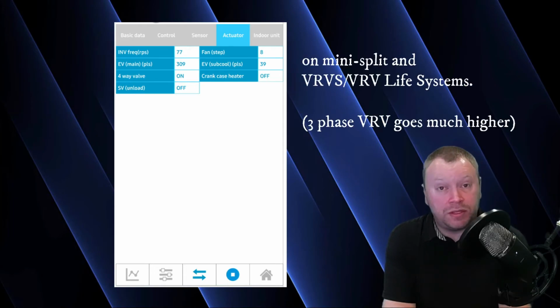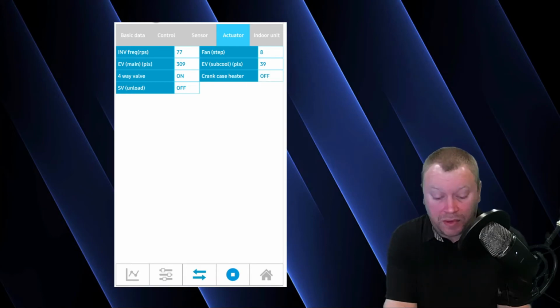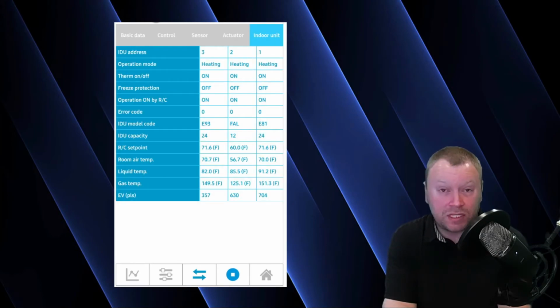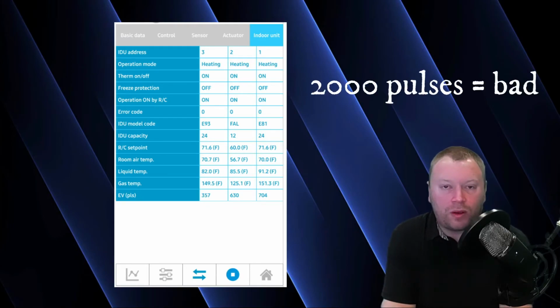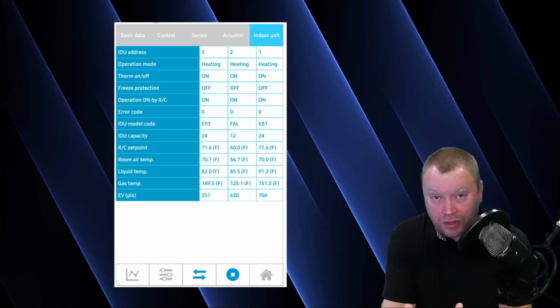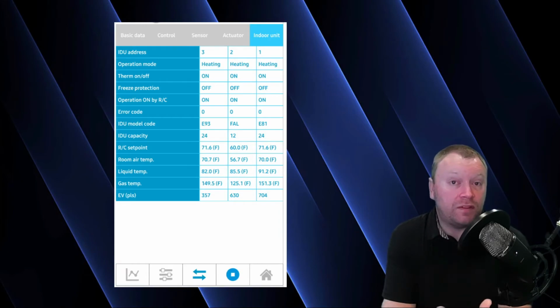And I didn't mention this a minute ago, but your indoor unit expansion valves, you'll see here 357, 630, and 704, they can go up to 2,000 positions. So you can see here, we're nowhere near that high-end mark. If your indoor unit expansion valve is ever at 2,000 pulses, by the way, that's usually a red flag. Why is it at 2,000? I like to really hone in on an indoor unit that's at 2,000 pulses and watch it carefully to make sure that if it does hit 2,000, it comes down very quickly.